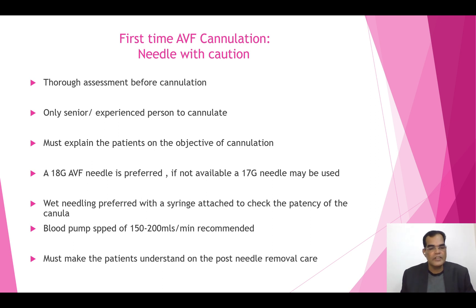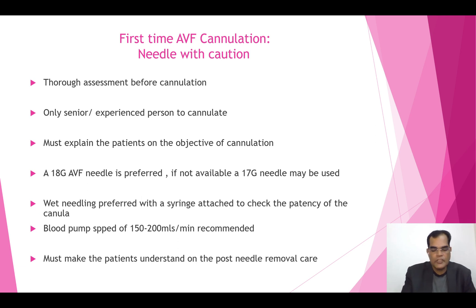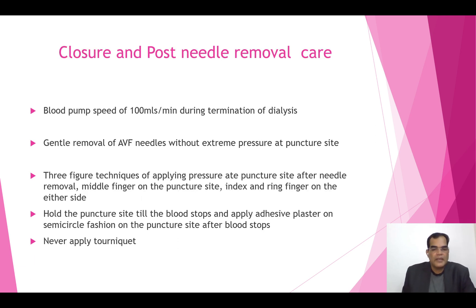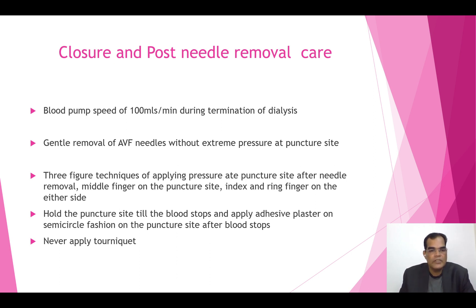Once dialysis starts, blood pump speed should not exceed 200 mls; ideally it should be about 150 mls. When returning blood to the patient, always stay at 100 mls per minute and do not exceed it, as this may create sudden pressure on the vessel. Even during termination of dialysis, exceeding this can cause a counterpuncture effect and swelling at the site.